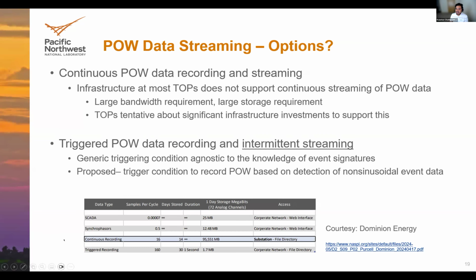Here's a snapshot from a Dominion Energy report comparing synchrophasors with continuous and triggered recordings of points on wave. For a single day with 72 channels, this entails about 95,000 megabytes of data, which is huge. This data also has to be transported from the substation to the control center, which is a challenge.